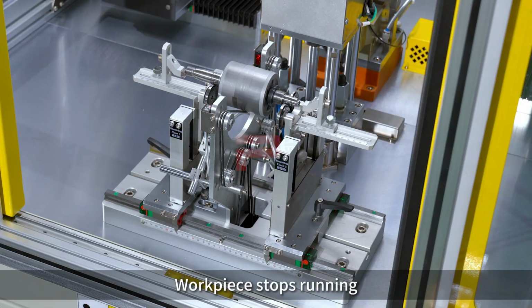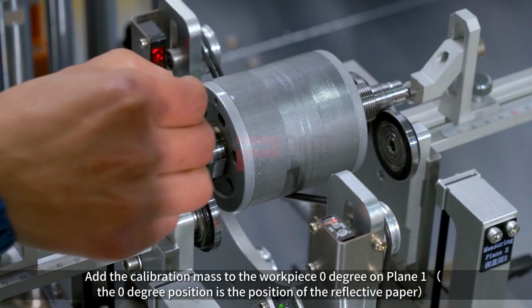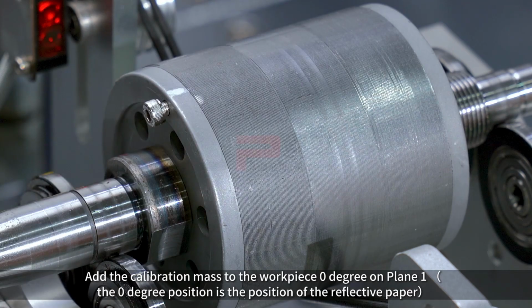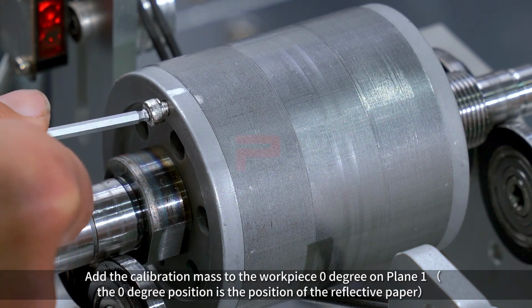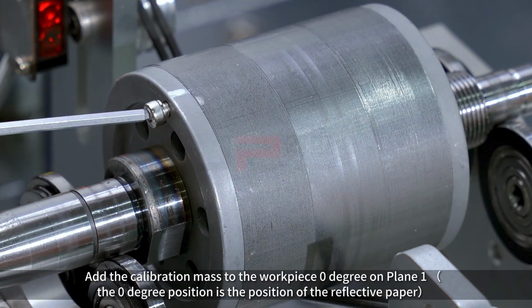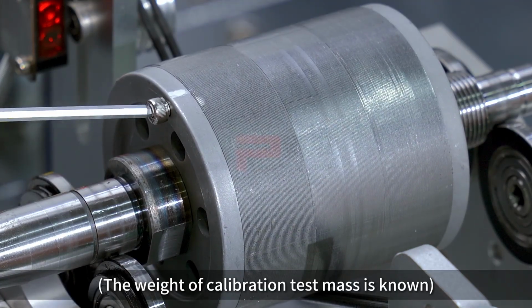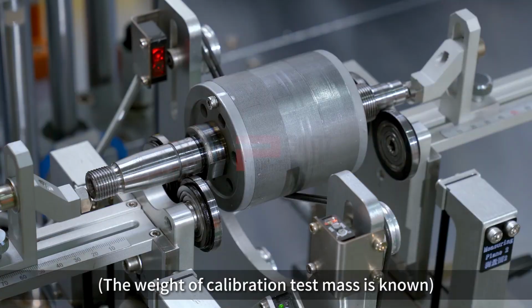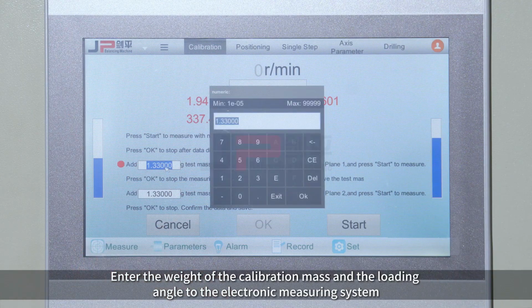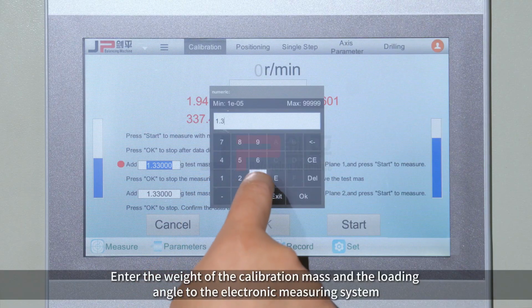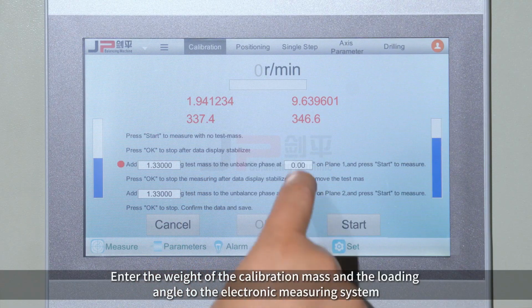The workpiece stops running. Add the calibration mass to the workpiece 0 degree on Plane 1. The 0 degree position is the position of the reflective paper. The weight of the calibration test mass is known. Enter the weight of the calibration mass and the loading angle into the electronic measuring system.